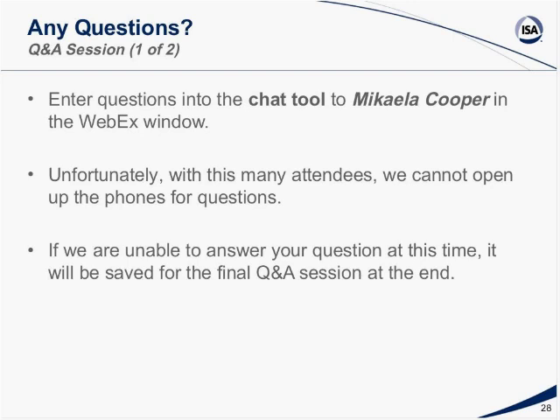Great. Next question. Is it appropriate and possible to design an automatic BMS involving no or minimal human intervention? Well, you always have to have the human intervention. In the case of an emergency, you have emergency push buttons to shut the process down. Otherwise, it's very common, particularly in smaller systems and in plants and office buildings, that there's no operator intervention. It's all done through just a start button, starts up and runs by itself. But in any boiler, you do have to have some way of manually shutting the system down if an incident is discovered and it's not shut down or does not go to a safe state automatically.